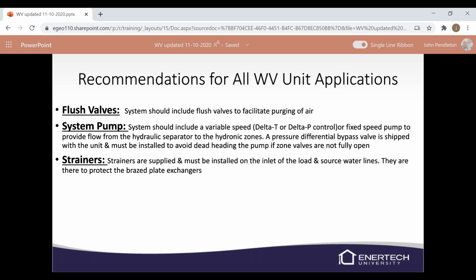Don't just say, well, I don't need to put those in. They're pretty important. The brazed plate manufacturer requires those, so make sure you're installing those strainers in the circuit in the proper direction of flow. Maybe put some valves near it so you can isolate it and clean it out as necessary as well.